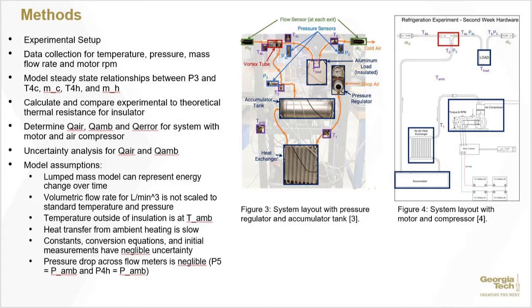The data collection will be run for temperature, pressure, mass flow rate, and motor RPM at various nominal PSI for the system with tank and the system with motor and air compressor, in order to characterize and model the steady state relationship between P3 and T4C, mass flow rate cold, T4H, and mass flow rate hot. These values are used to calculate Q air, Q ambient, and Q error for the system. Also, uncertainty analysis for Q air and Q ambient will be conducted based on instrumental uncertainty, precision and accuracy, and error propagation analysis to determine the system's capabilities.